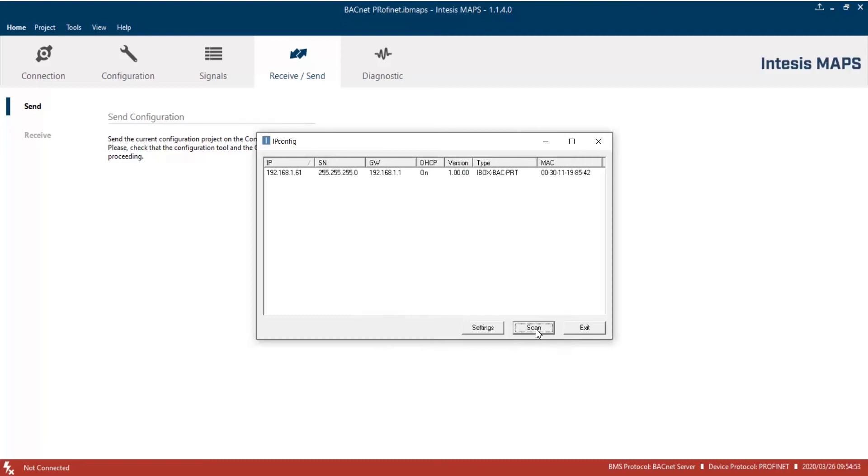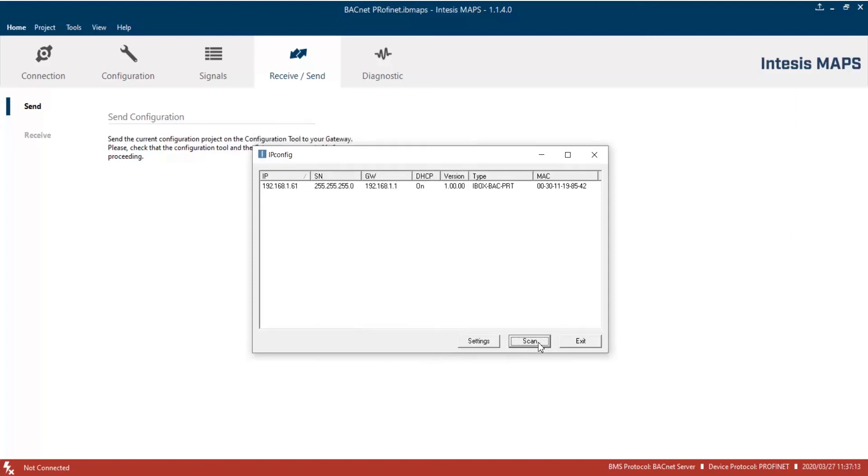Okay, now configuration is finished. So, let's check that all the setup we have done is working properly. To do so, we will use Yabe as a BACnet client and Profinet master simulator as an IO controller.